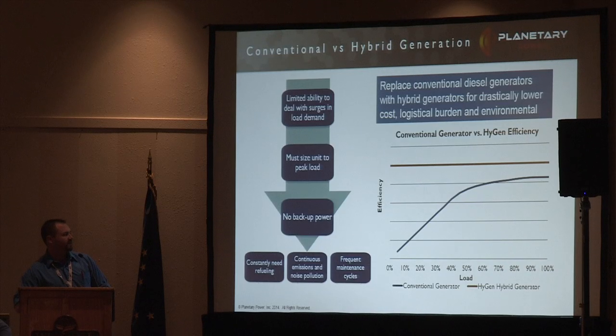It might be a little bit extreme, but I did that to illustrate the difference between a hybrid system and a diesel generator. A diesel generator's efficiency drops off quite a bit, where a hybrid system can be just as efficient charging my iPhone as it can be supplying its rated load. We do that through energy storage — I'll talk about that in a bit — but you have to size it to your peak load.